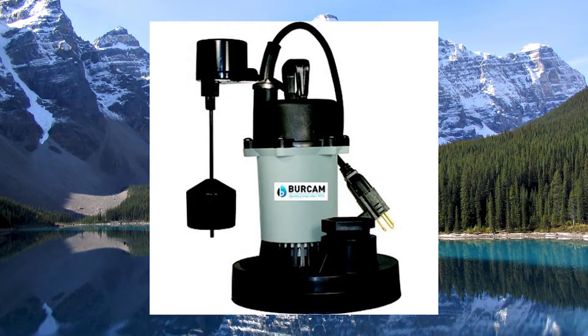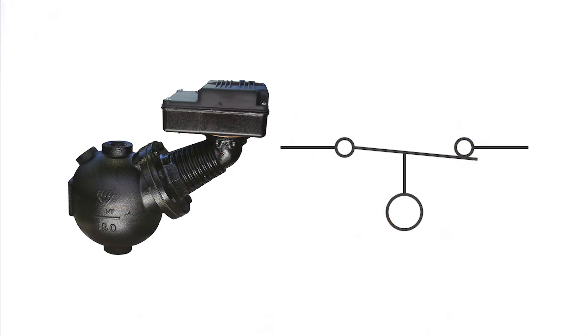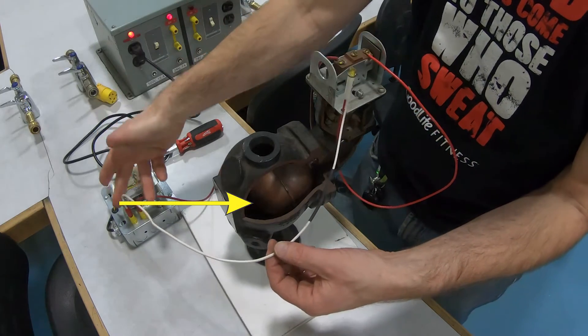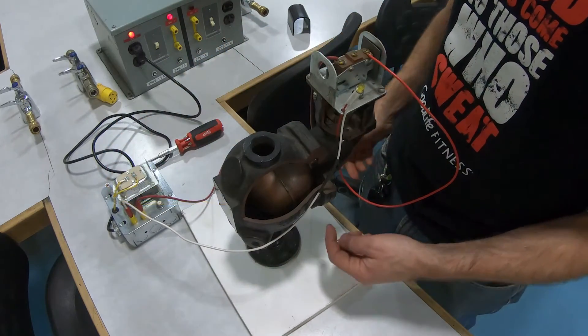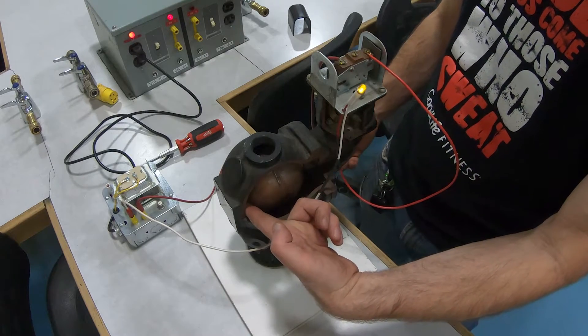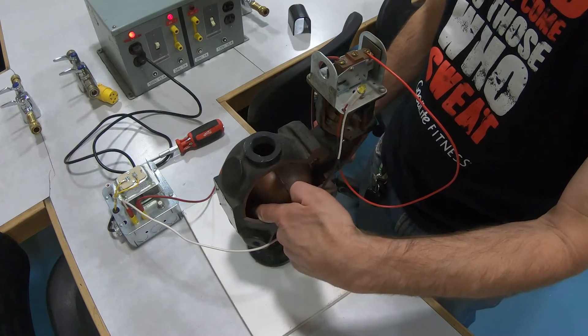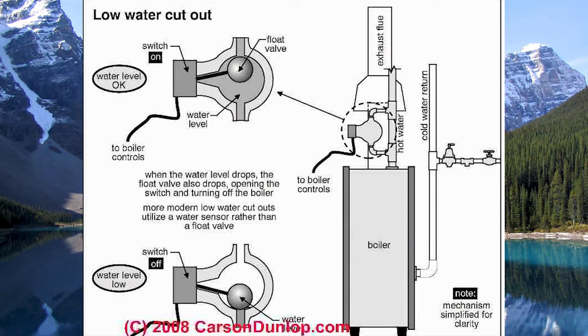The next type of device we come across in the field is a level sensing switch. A low water cutoff is a really good example of this. We have a ball float in there, and when the water from the system gets high enough, the ball floats up and the switch is closed. Notice that the LED light came on. This is useful in boiler systems where we want to protect the boiler from having low water conditions.